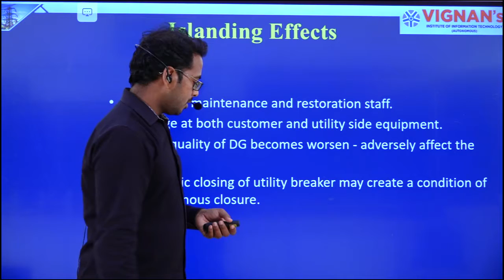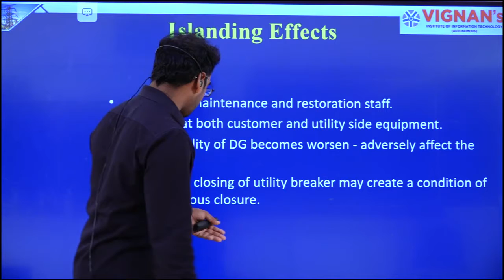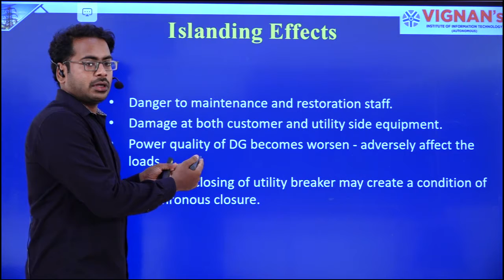And the automatic closing of the utility breaker may create a condition of asynchronous closure. That means when the particular EPS, the electrical power system, goes into a sudden islanding condition, it is disconnecting from the grid. The automatic closing of the utility breaker may create a condition of asynchronous closure. It must be a synchronous closure, but in this unexpected, sudden islanding condition, it acts as an asynchronous closure. These are some of the effects because of sudden islanding condition.